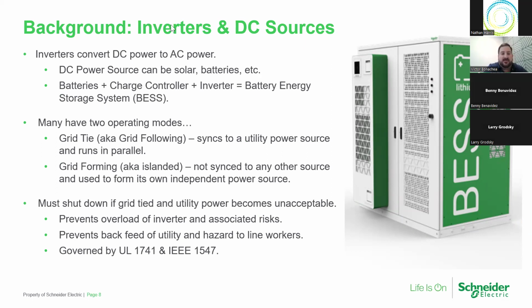Inverters overall are there to convert DC power to AC power. That's with rotating machines, it's inherently AC power right off the bat. But when you have DC sources like solar panels, like batteries, maybe other things out there like fuel cells, most of our electrical systems today operate on AC in our distribution systems and facilities. So you need to get that over to AC to really feed it throughout your facility. So that's the job of the inverter. And what the DC source is behind the inverter doesn't really matter. The inverter gets DC power, and it can be coming from any of those DC sources, the solar, the battery, whatever.